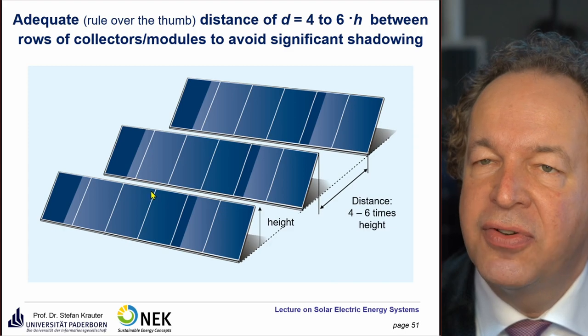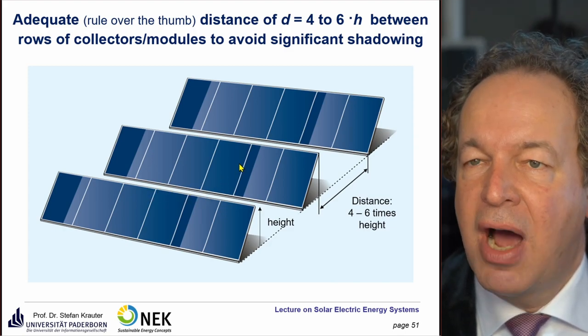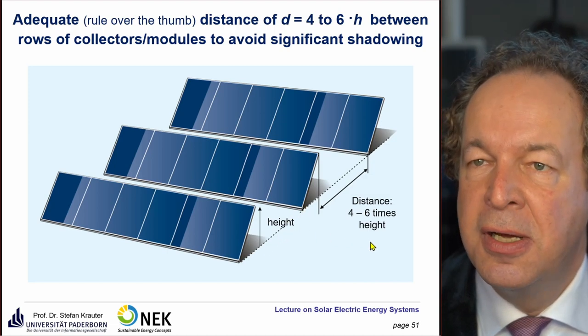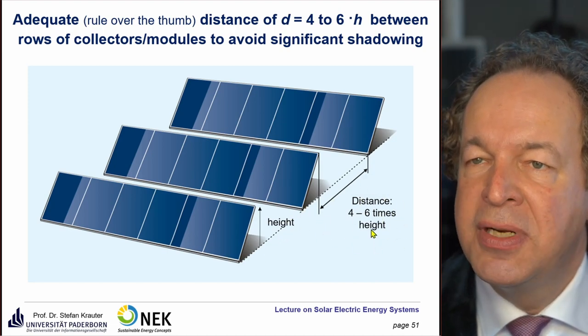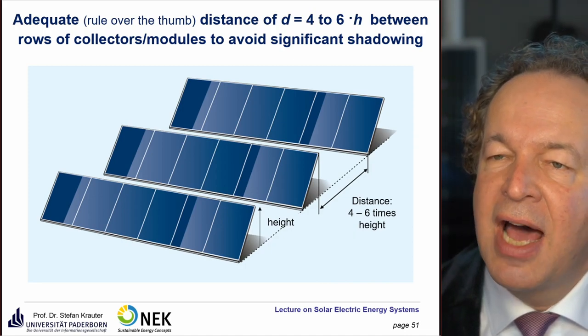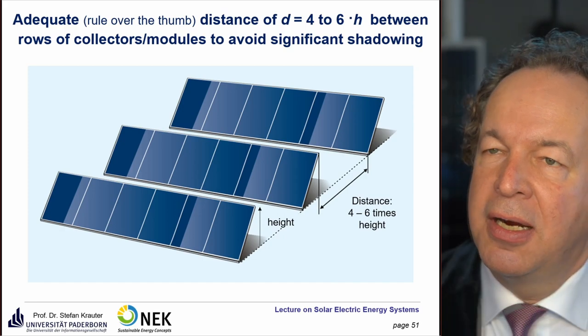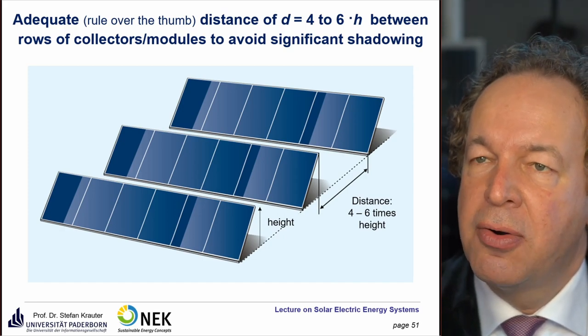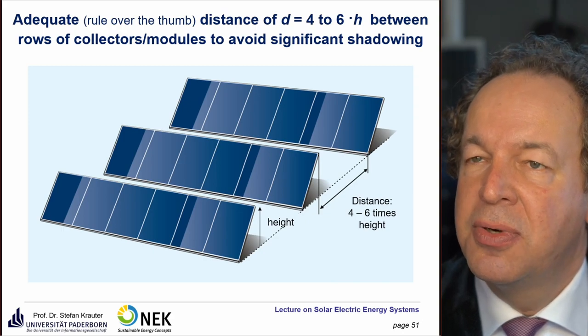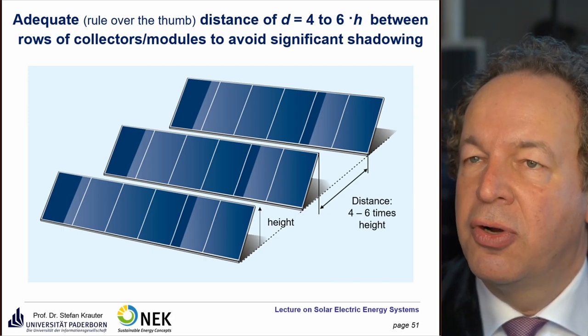In winter around the 21st of December, the sun elevation angle in Paderborn is only about 14.7 degrees, so the shadow cast is rather long. You must maintain a very large distance between rows. A rule of thumb for Germany is to keep a distance of four to six times the height — a compromise between energy loss from shadowing and land area loss.